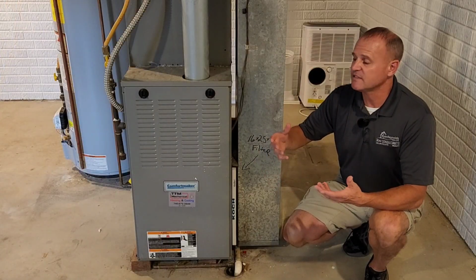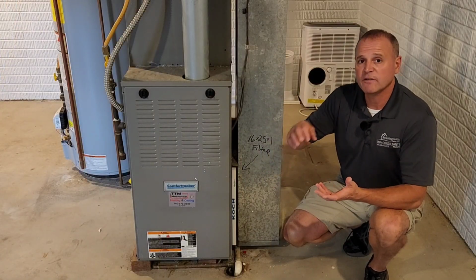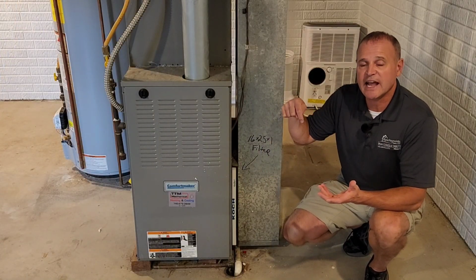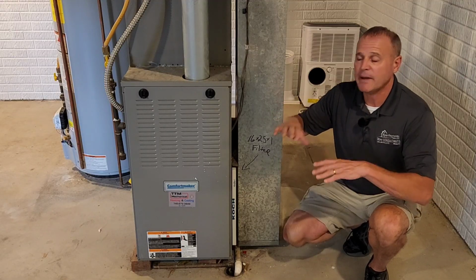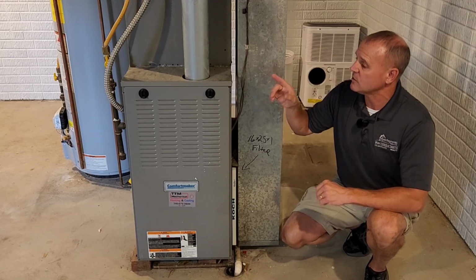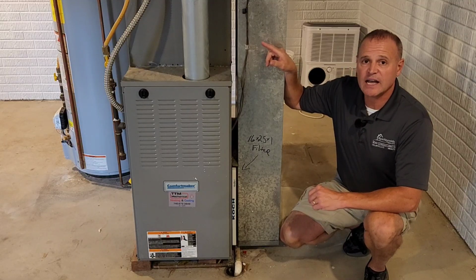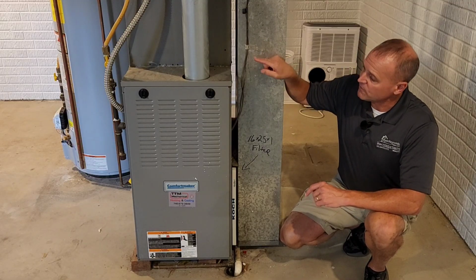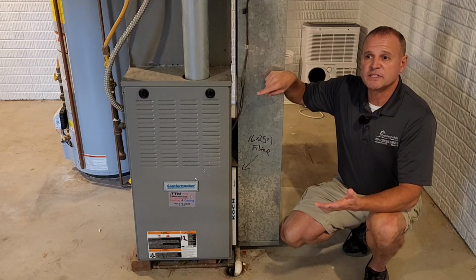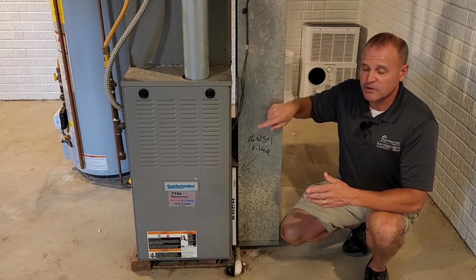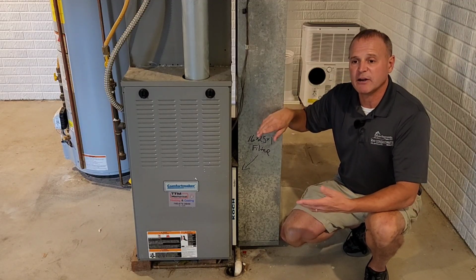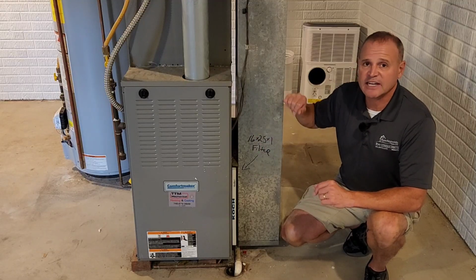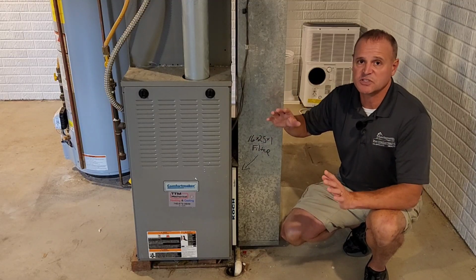Well, one of the results of cooling air is that it produces moisture that condenses onto the A coil, and then that water has to go somewhere. If that drain line gets clogged up, or if the opening from the tray into the actual drain line gets clogged up, then water can back up inside the furnace. One of the bad things about the way these are designed, with the A coil on top, is that if water gets backed up, it can overflow and go down into the furnace part, which could start to corrode your heat exchanger. It could get into your fan and cause problems with the bearings or even corrosion there. And it can also get into the electronics, which could immediately just toast the furnace.